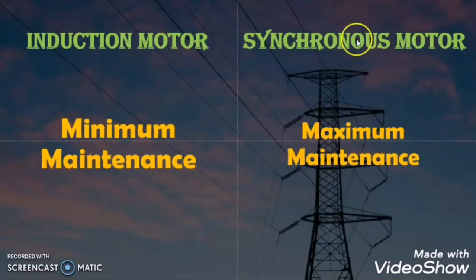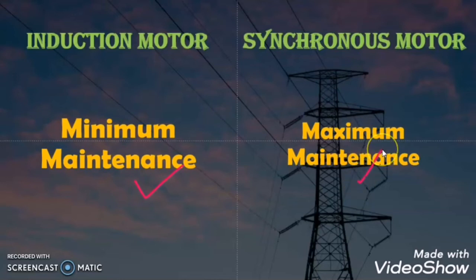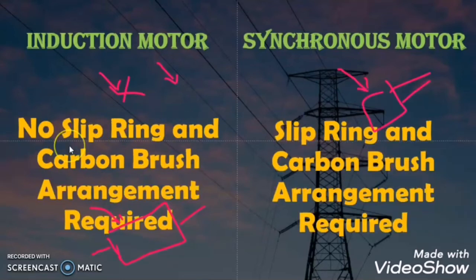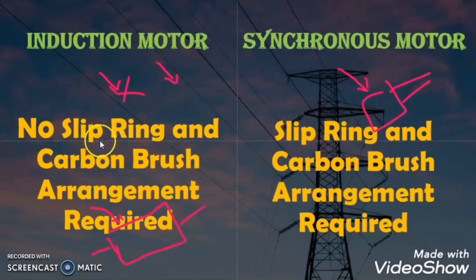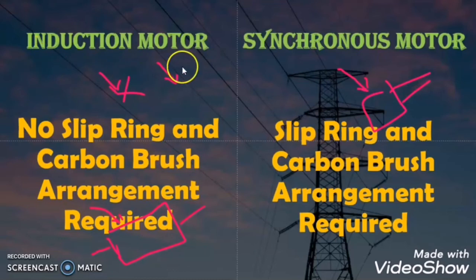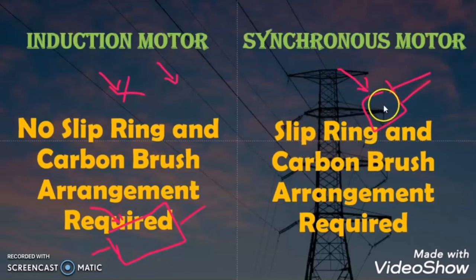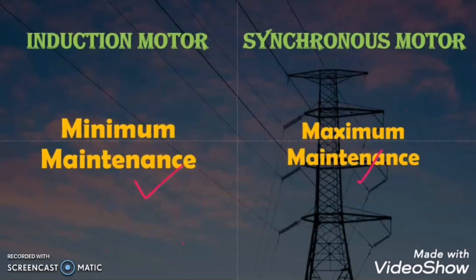The other difference is that the induction motor requires minimum maintenance, but the synchronous motor requires maximum maintenance. The reason is simple: wherever slip ring and carbon brush arrangement is involved, there is a lot of maintenance. In the induction motor, especially the squirrel cage type, there is no slip ring requirement, which is why it is called a maintenance-free motor. That is why the squirrel cage induction motor is the most popular motor throughout the world.